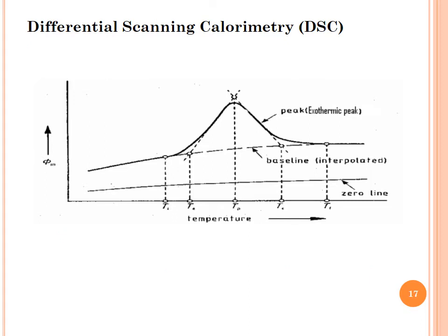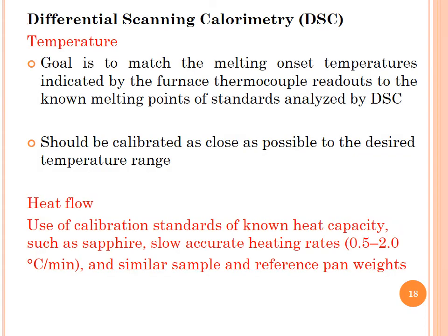The amplified DSC signal is automatically varied with temperature to maintain constant calorimetric sensitivity. In the baseline correction graph, there is a zero line, a baseline interpolated, and an exothermic peak. The maxima represents exothermic and the minima represents endothermic events in DSC curves. For temperature calibration, the goal is to match the melting onset temperatures indicated by the furnace thermocouple readout to the known melting points of standards analyzed by DSC, calibrated as close as possible to the desired temperature range.